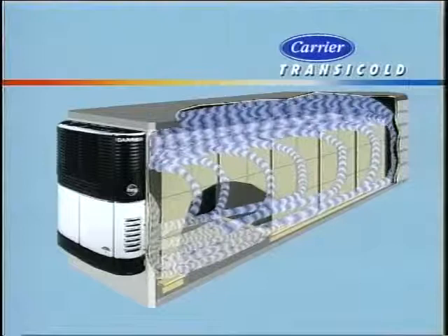The defrost cycle will last from 5 to 20 minutes, depending on how much ice is on the evaporator coil. The unit should be manually defrosted once a day, and more frequently when the trailer is loaded with a warm, moist product such as fresh produce. Manually defrost the unit right after loading is complete, and again later if the box temperature is not coming down to set point as quickly as usual.